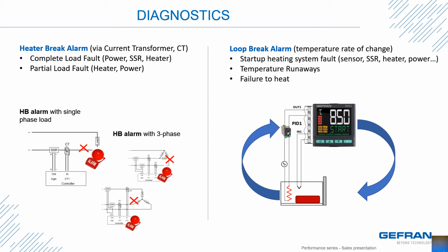Loop break alarm is a different concept than heater break alarm. Loop break alarm is monitoring temperature rate of change as compared to the output. In my opinion, this feature is best used in startup situations where runaway temperatures can occur during long unsupervised heat-ups. The controller is looking at the output status, and from that it looks for corresponding increase or decrease of temperature over time. Given this situation, the controller LBA function, loop break alarm, is only active when the output is outside of the proportional band. The controller output must be fully on or off. That's why I say it's best in startup situations.